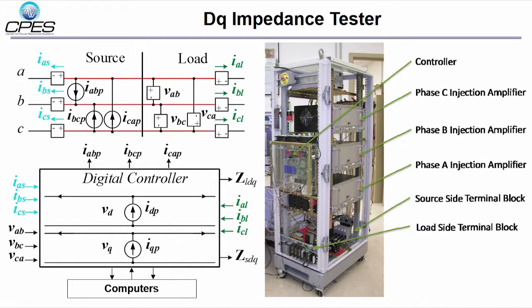The principle of the tester can be simply explained by this diagram. The computer gives the measurement command to the digital controller. Digital controller first synchronizes with the system to be tested. Then it gives the perturbation in DQ frame. These perturbation signals are injected to the system by transferring them to ABC frame.